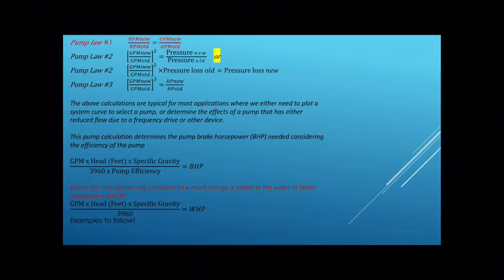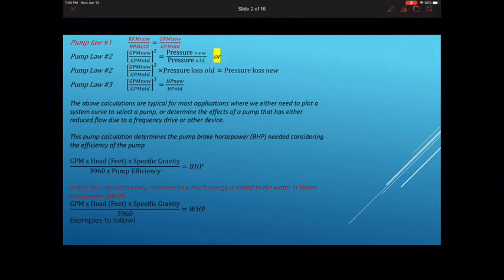All right. So there's essentially 3 pump laws, and I want to look at identifying each one of these things. So the first pump law that we deal with is up on the top, right there. That particular pump law identifies that RPM and the flow rate go directly proportional. It's kind of a 1-to-1 ratio is how they function.